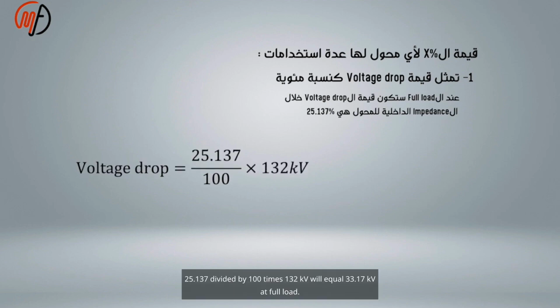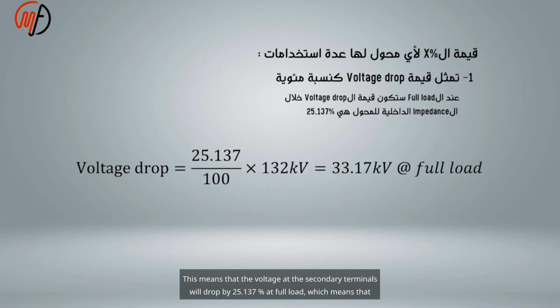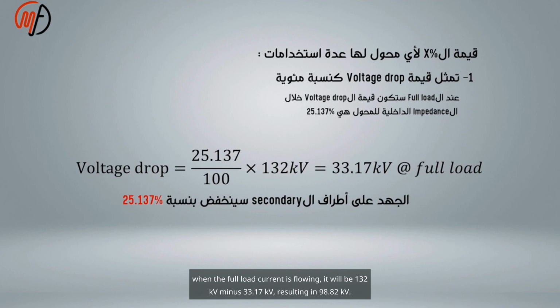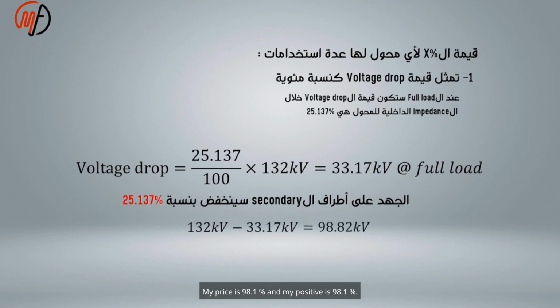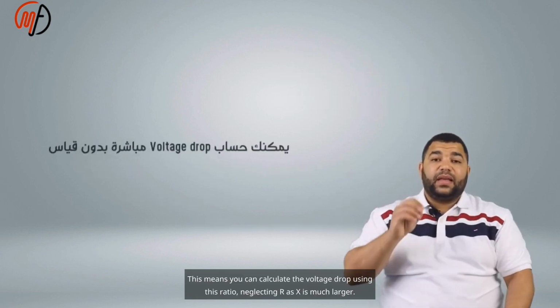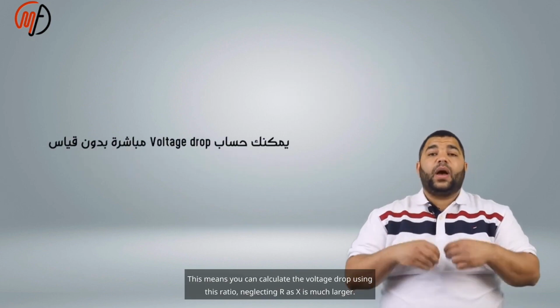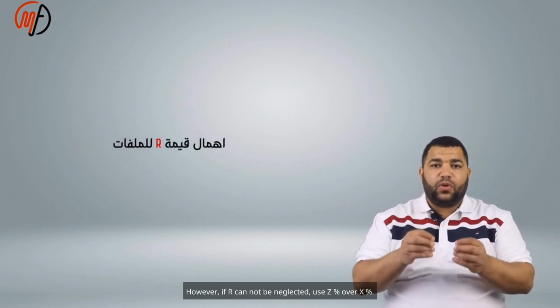25.137 divided by 100 times 132 kV will equal 33.17 kV at full load. This means that the voltage at the secondary terminals will drop by 25.137% at full load, which means that when the full load current is flowing, it will be 132 kV minus 33.17 kV, resulting in 98.82 kV. This means you can calculate the voltage drop using this ratio, neglecting R as X is much larger. However, if R cannot be neglected, use Z% over X%.